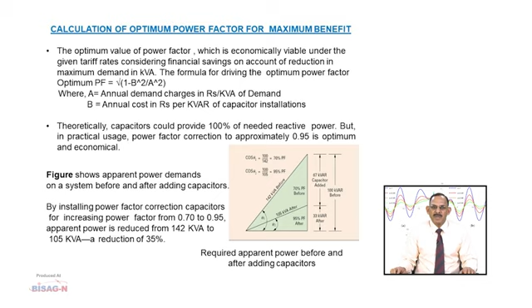kVAr of capacitor installations. Theoretically, capacitors can provide 100% of needed reactive power, but in practical use, power factor correction to approximately 0.95 is optimum and economical. The figure shows apparent power demands on a system before and after adding the capacitor. By installing power factor correction capacitors for increasing power factor from 0.70 to 0.95, apparent power reduces from 142 kVA to 105 kVA, that is a reduction of 35%.